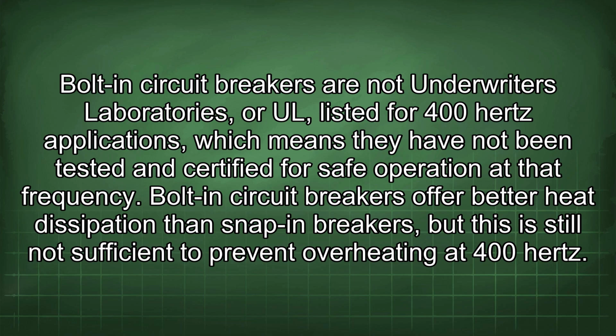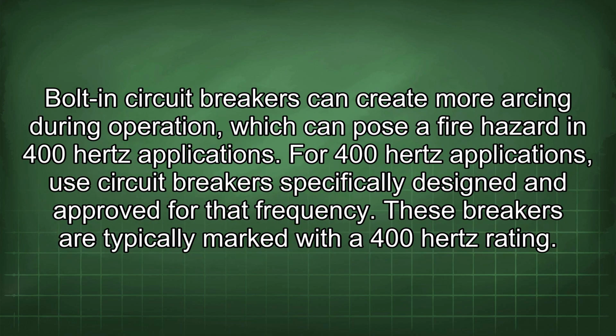Bolt-in circuit breakers offer better heat dissipation than snap-in breakers, but this is still not sufficient to prevent overheating at 400 Hz. Bolt-in circuit breakers can create more arcing during operation, which can pose a fire hazard in 400 Hz applications. For 400 Hz applications, use circuit breakers specifically designed and approved for that frequency. These breakers are typically marked with a 400 Hz rating.